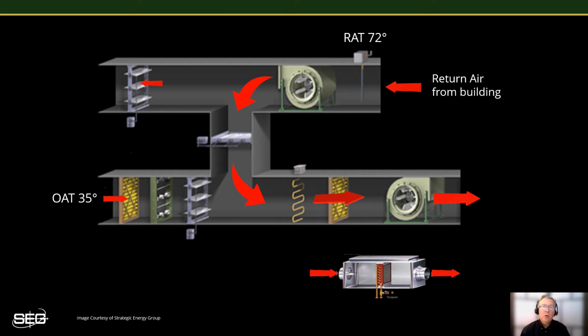So let's see how that works. Let's make a change with the controls and move the supply air set point upwards in temperature to 65 degrees. And let's see what happens throughout the system. Notice how the outside air damper now drops to only 15% open. This decreases the amount of cold outside air being brought in and utilizes more of the warm return air. And then notice the mixed air and supply air temperatures have now risen to 65 degrees.